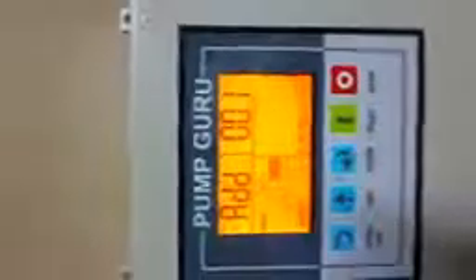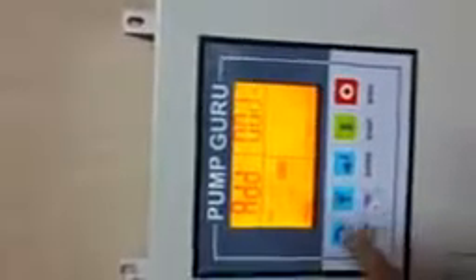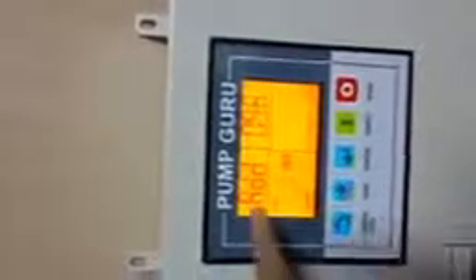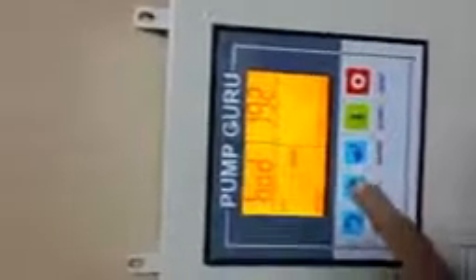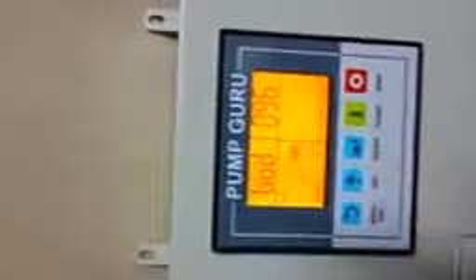when you are dealing with big buildings or industrial premises, you can set communication on this product. So this is going to communicate to a third party on a PC for SCADA visualization, and here the Modbus address will be defined. You can change the Modbus address. You can set the baud rate, you can go to 9600 or 19200, and you can set it. This is the way it is going to get connected to a PC, and it shows that all the parameters of the pump are transferred to the PC, or some of the commands can be received from a PC to the pump controller for the operation.